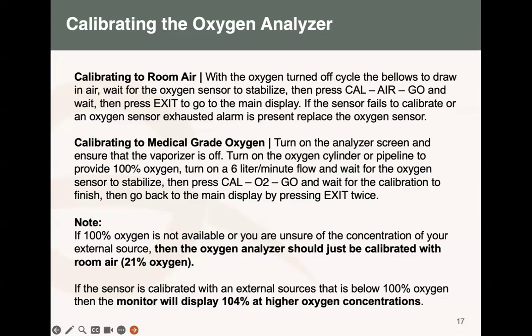because when you calibrate with an oxygen percentage which is not 100%, in the event the machine produces a higher oxygen percentage than what you have calibrated with, the machine will display more than 100, maybe 104. And basically, it doesn't mean that you have more than 100 oxygen in the system. It means the reference you gave the machine was lower than what is actually being produced now. So we really advise, if you don't have 100% oxygen, please only do the air calibration.